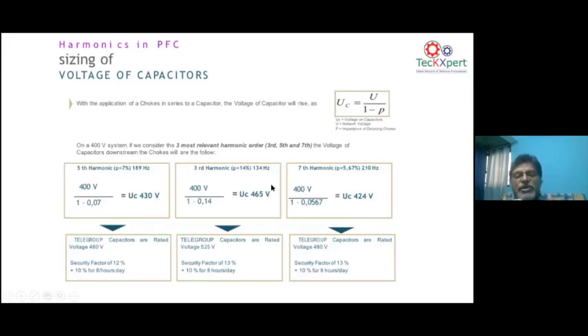Now, again, your network does not have to remain steady at 415 volt. Your network voltage also keeps varying between plus 10% and minus 10%. So that means you have to always ensure that this is also taken into account when you are designing the capacitor kVAr in the low voltage. So in the low voltage, you either go with a 480 volt or a 525 volt in the Indian context, depending on whether we are using 7% or 14%, because the network voltage keeps fluctuating.